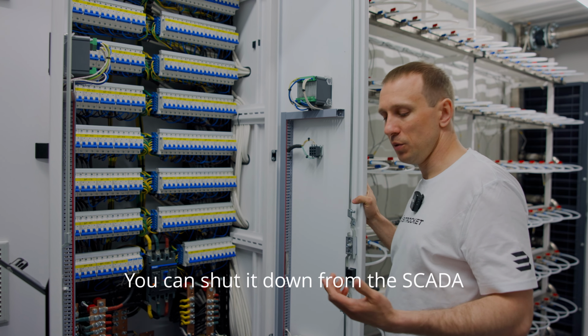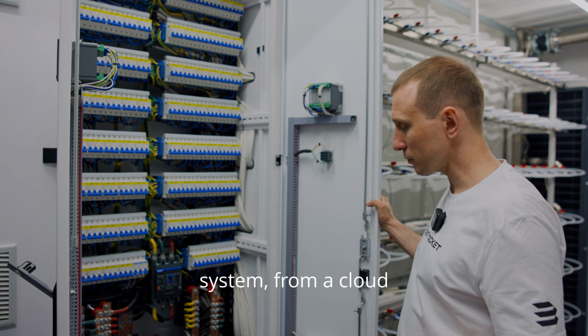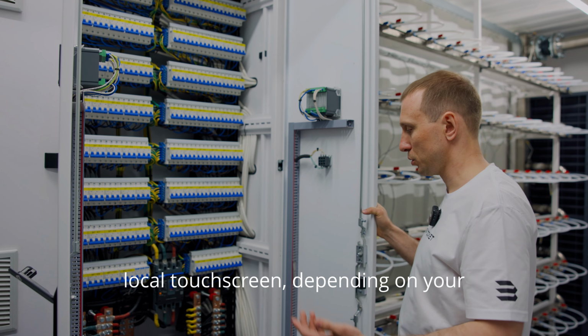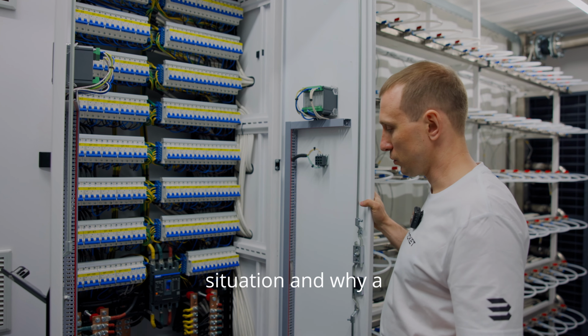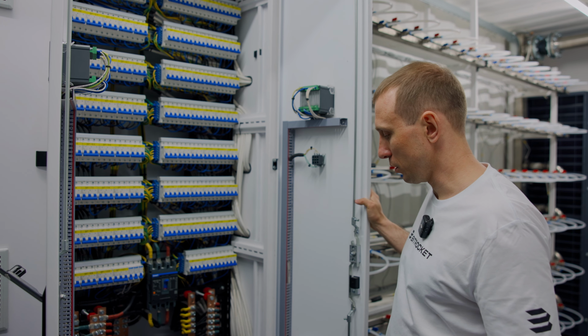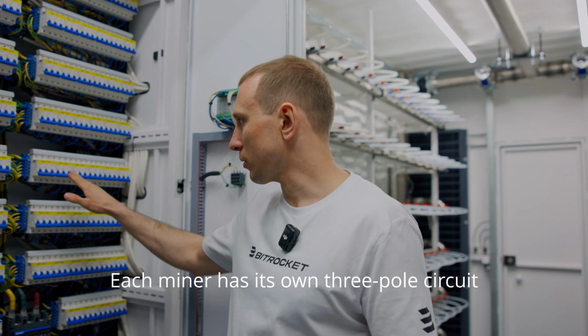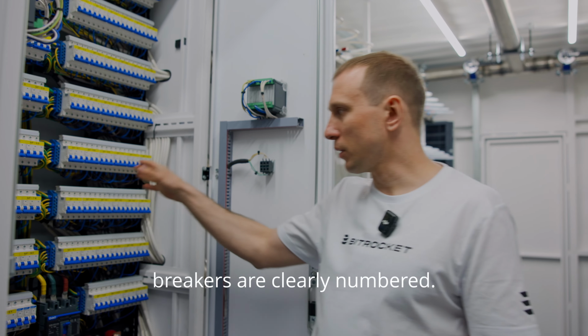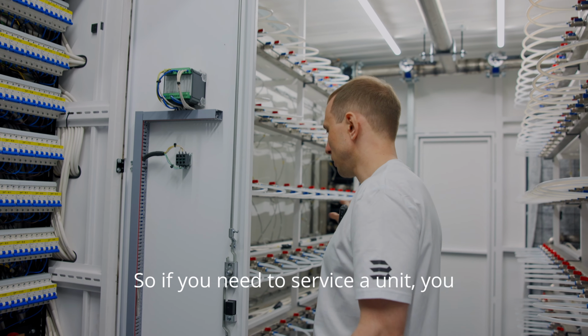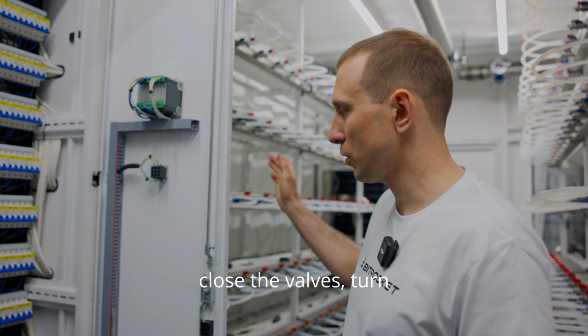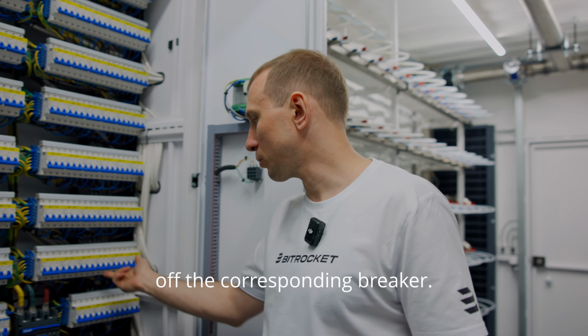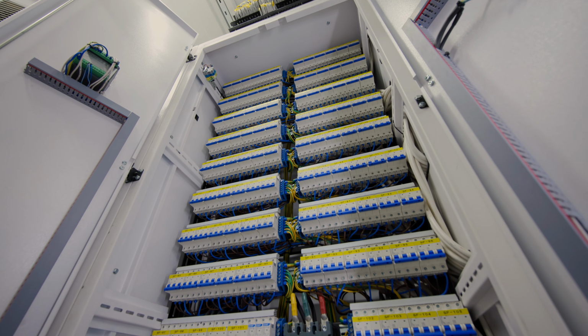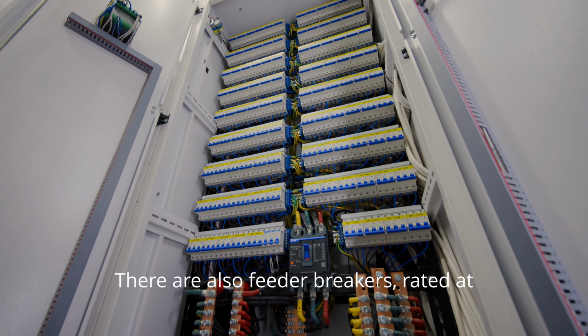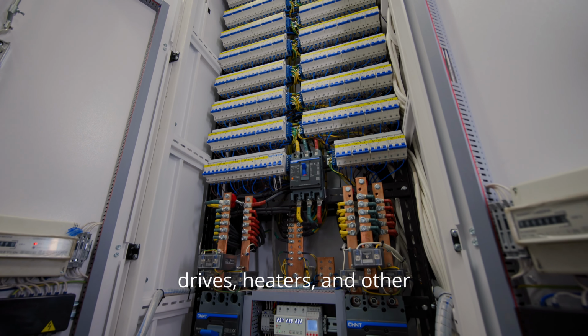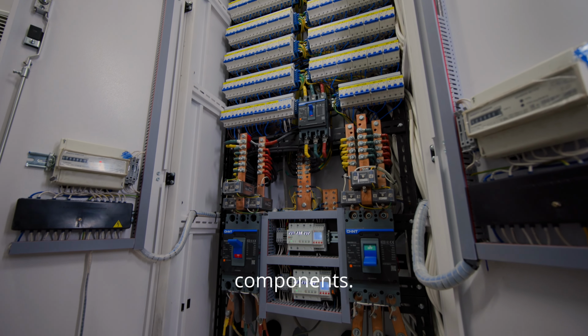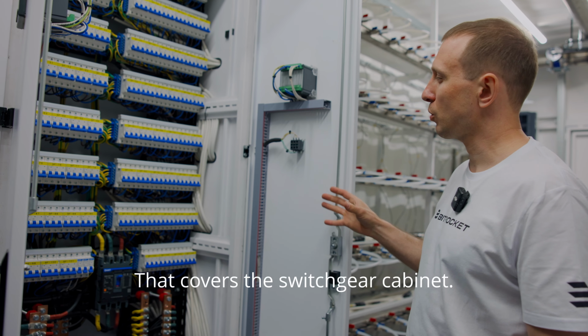You can shut it down from the SCADA system, from a cloud service, or directly from the local touchscreen, depending on your situation and why a shutdown is necessary. Each miner has its own 3-pole circuit breaker, and all breakers are clearly numbered. So if you need to service a unit, you close the valves, turn off the miner, and switch off the corresponding breaker. There are also feeder breakers, rated at 160 amps for frequency drives, heaters, and other components. That covers the switchgear cabinet.